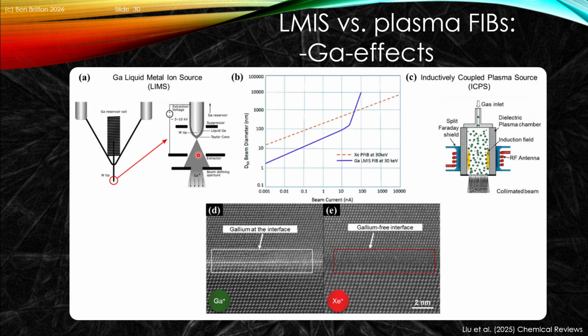So we can see this in terms of the spot size and currents. We can see this in terms of how we get different resolutions. This is a related picture to what we had. But one of the reasons why we might want to avoid gallium in our system is that gallium can collect on the interface when we prepare a sample. This is an atomic resolution, I think it's a STEM image of a system. And so here this gallium can enrich itself, and so we get a sample preparation artifact due to the decoration of gallium at this interface. If we prepare the sample with xenon FIB, we see that we do not have that enrichment of gallium. And so this is one example where there is an improvement because we don't have sample prep induced defects in our system.